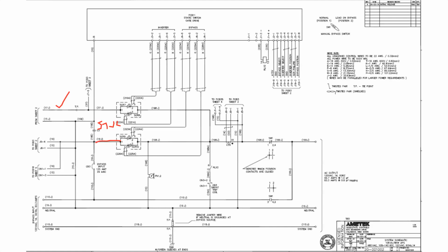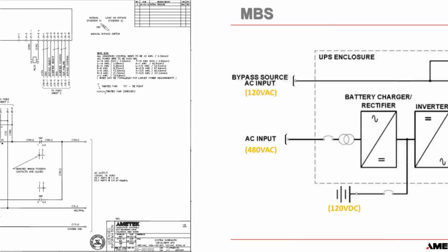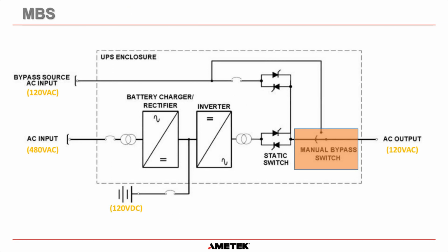Because remember, if we are on inverter and we want to transfer to bypass, what happens is when we press the bypass to load button, or the system does it automatically, this static switch comes on first. So these two static switches will be on at the same time. So they have to be identical waveforms or there would be circulating current. So they are identical because they're in sync. And then as soon as this one turns on, this one will turn off. And therefore it is a seamless transfer.